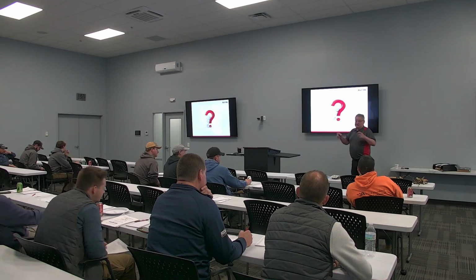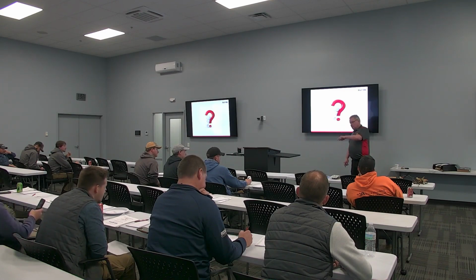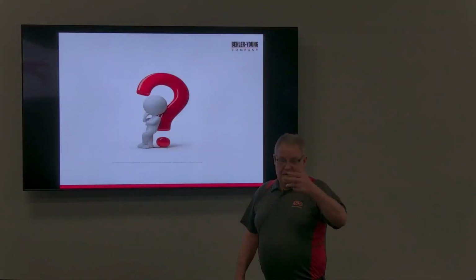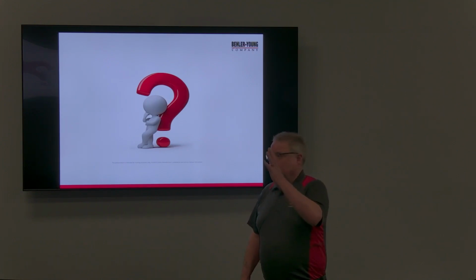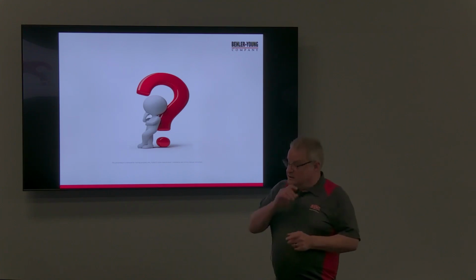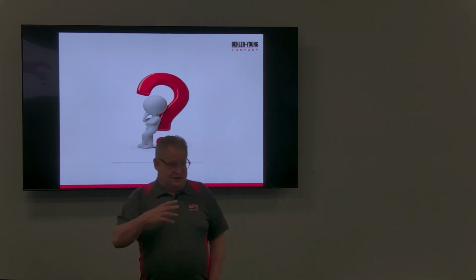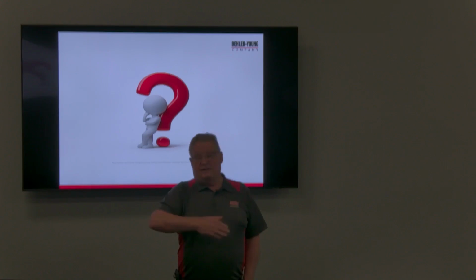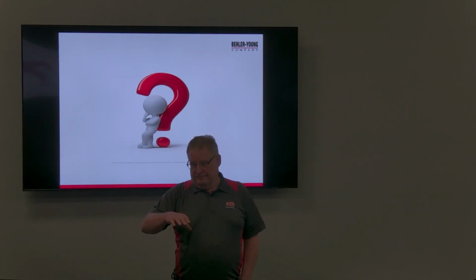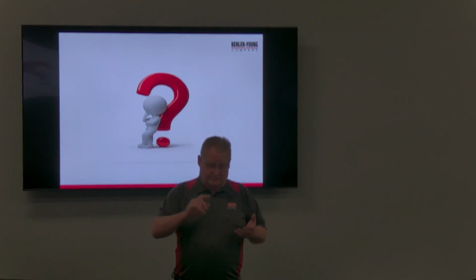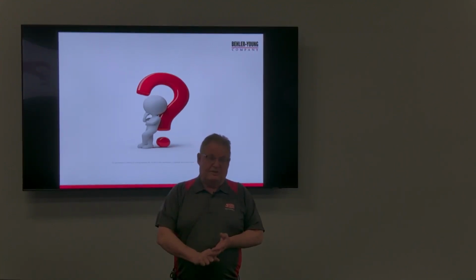So when you're replacing contactors, make sure you put back the one that's supposed to have that cover over it. I know you probably carry contactors in your truck that are the same, but they don't have the cover. That's a lot of liability, switching to that other contactor. The good news is Mars, who we get our generic contactors from, is starting to switch all their contactors to have that cover. Eventually your generics will be that way too, but in the meantime you want to replace it with the same contactor. You don't want to have that type of responsibility.